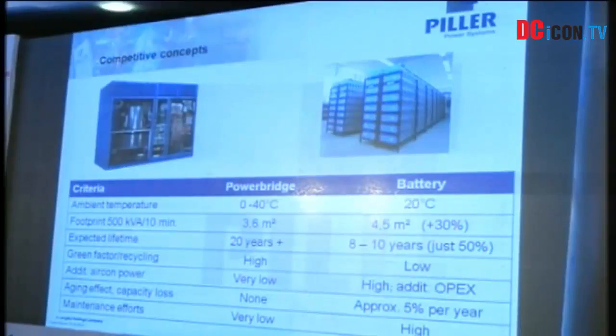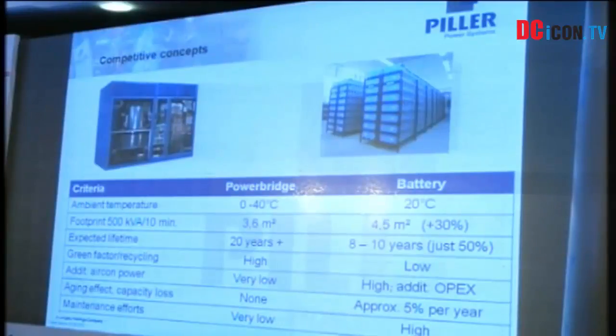Okay. Now here is a comparison between a power bridge, or a kinetic energy storage, against a battery. As I said, batteries require a very cool environment, but flywheels or power bridge don't require a cool environment. So ambient temperature 0 to 40. What does this mean? You don't have to have cooling equipment. You don't have to spend energy in cooling every day. Cooling expenses are very, very high in a data center, so you don't need cooling for these. The footprint for a 500 kVA 10-minute battery system is 4.5 meters square, whereas a flywheel is just 3.6 meters square, which is almost 30% lower than a battery requirement.